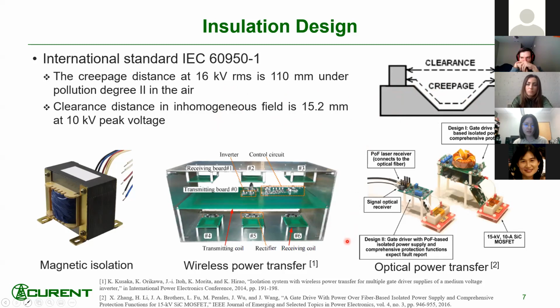What is most commonly used in power electronics applications to do this insulation design falls into 3 categories. One is the usual magnetic isolation. So it's a transformer. There will be a core, primary windings, secondary windings, and insulation material in between to maintain the insulation. Another is wireless power transfer. As you can see here, the transmitting coils and the receiving coils are separated at a distance, so they use air as an insulation. And the third is using optical power to support the gate driver.